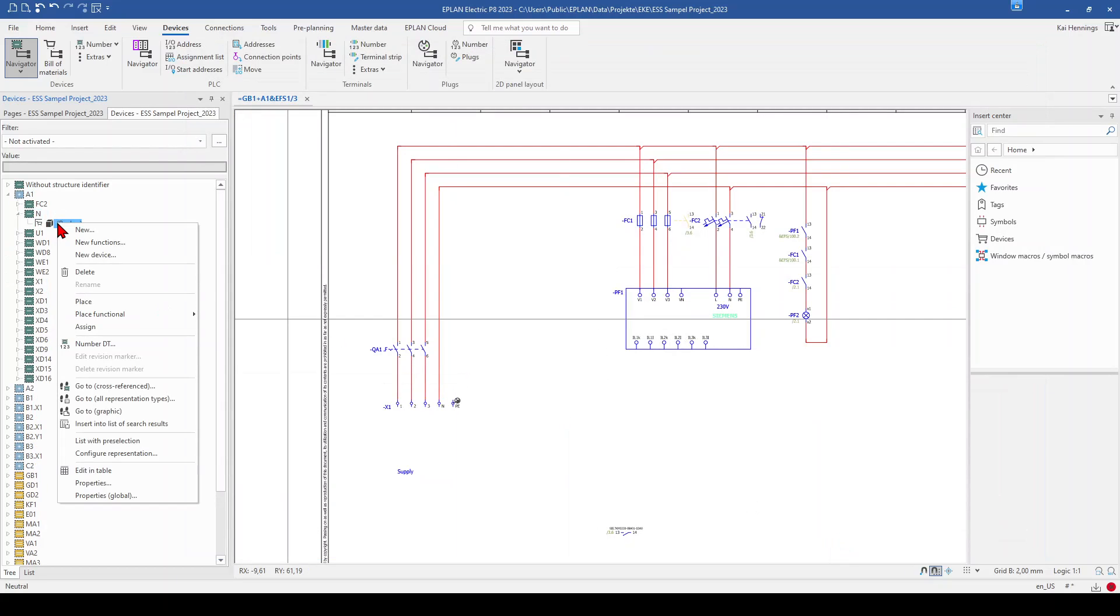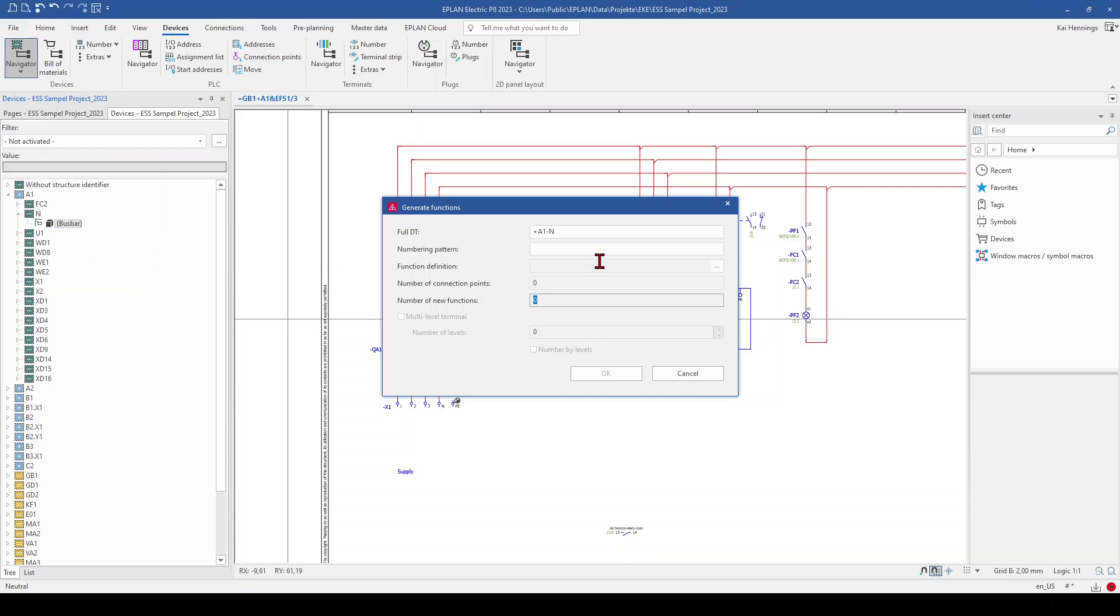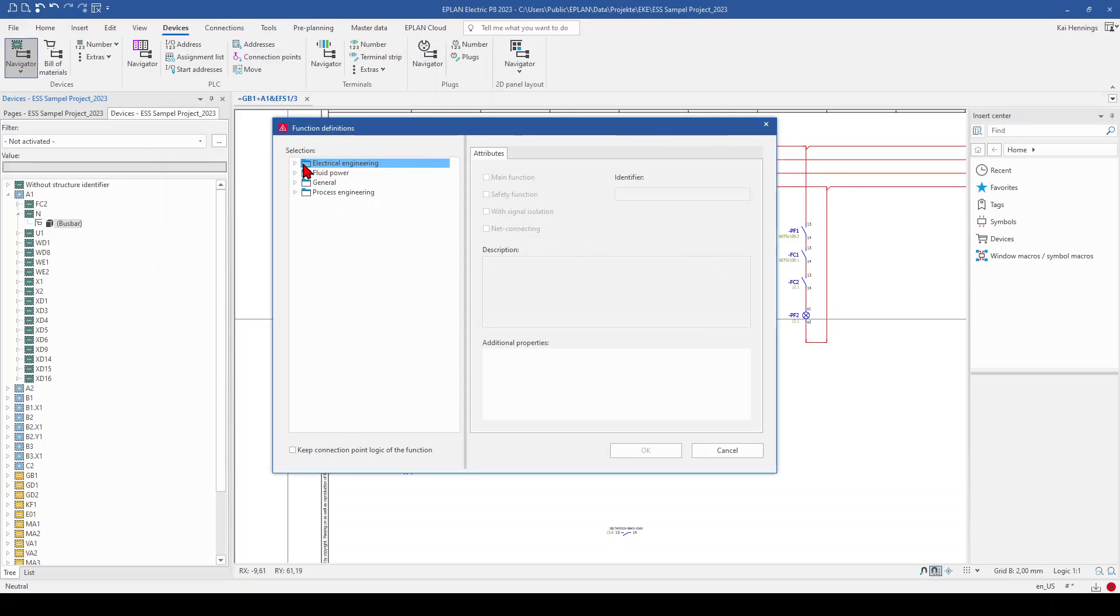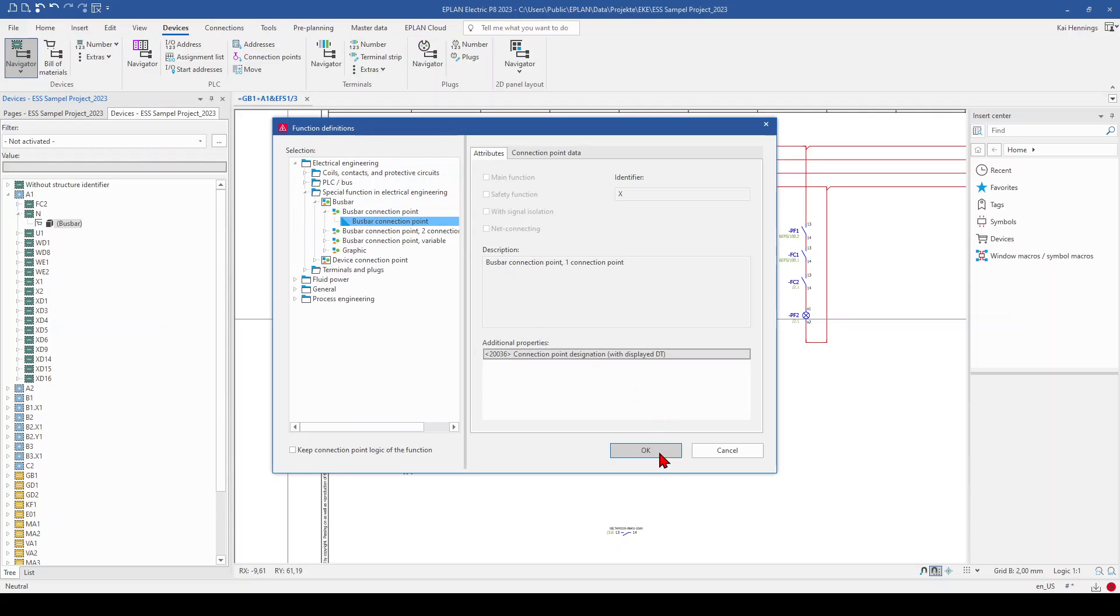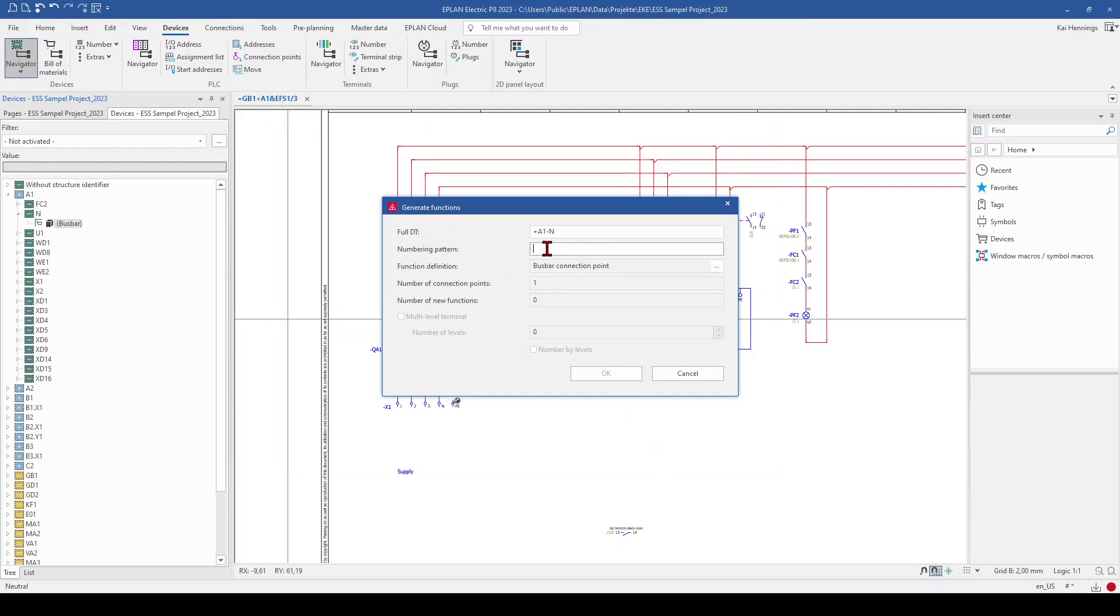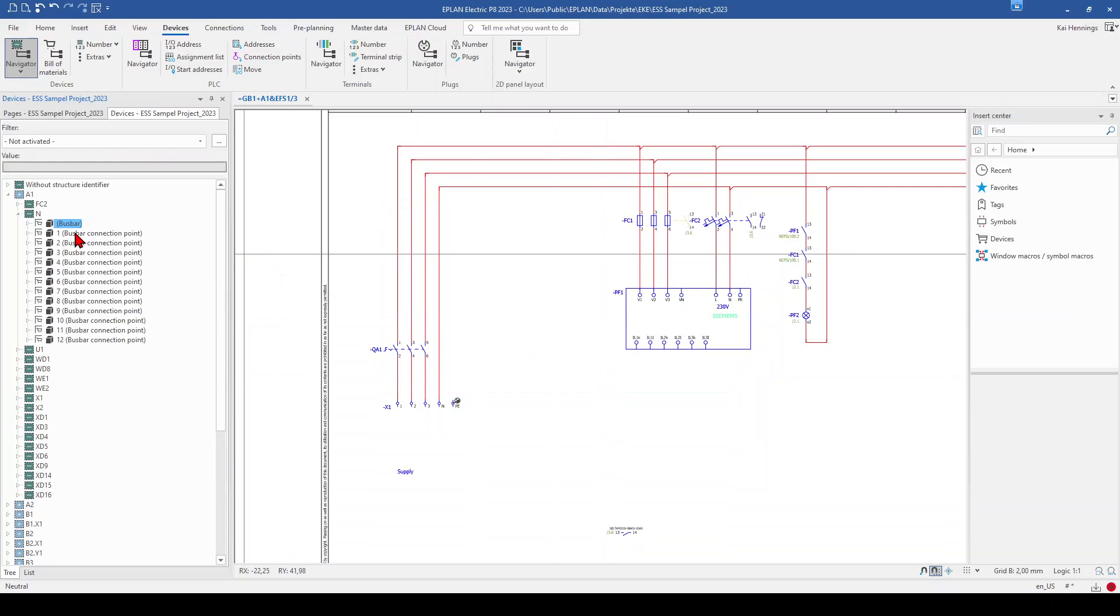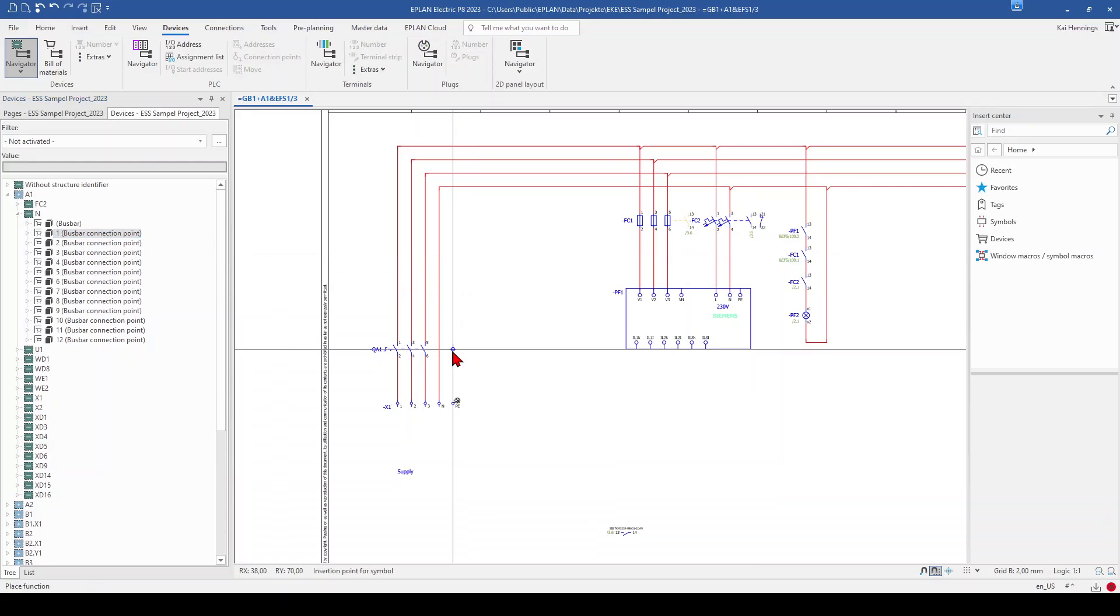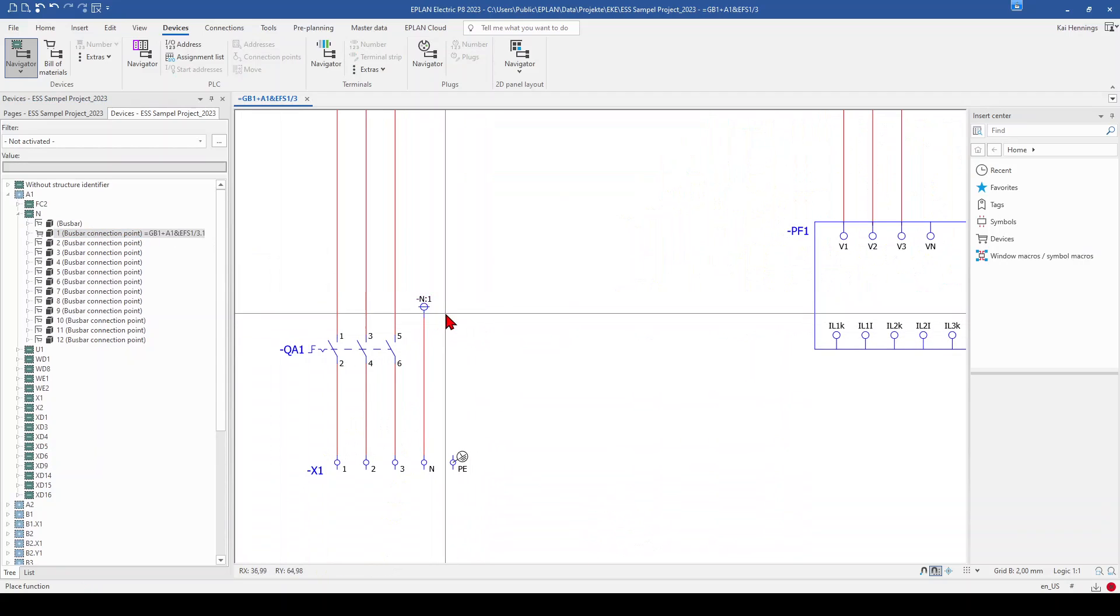And here we make now a right click and click on new functions. And we set the function definition to the busbar connection. And because we know that we have 12 poles, we make the numbering format from 1 to 12. And then you see that ePlan automatically counts the number of functions to 12. And we click OK. And now we have in our device navigator 12 neutral busbar connections under this device. So we can insert them, tap you can rotate it and place it for example here on our neutral.